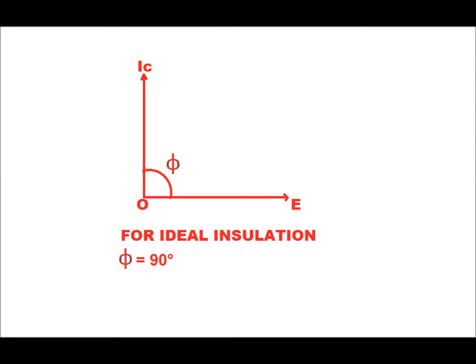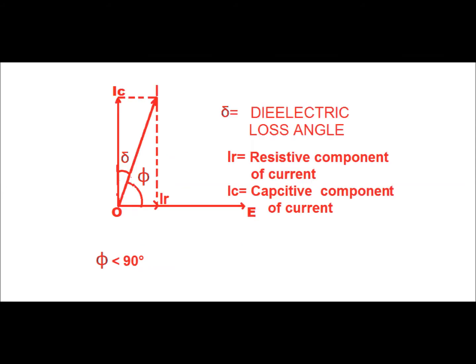An insulator can be considered as a capacitance. In the ideal case, the capacitance current IC leads the voltage E by 90 degrees — phi is equal to 90 degrees for ideal insulation. But in practice, there is no ideal insulation; there exists some leakage current IR, and that is in phase with the applied voltage E.